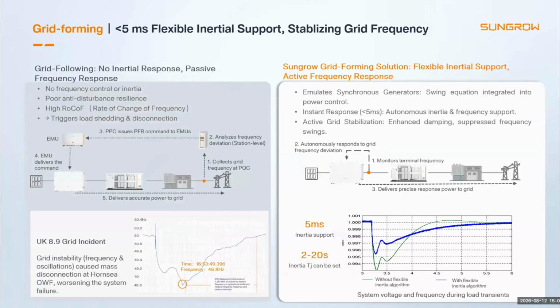One important grid forming function is the inertia support. Unlike synchronous generators, PV inverters have no physical rotating mass. Sungrow therefore emulates synchronous generator behavior through control algorithms. The inverter can respond to frequency changes within 5 milliseconds, providing very fast virtual inertia. Because this response happens locally at inverter level, it is much faster than waiting for a plant controller to measure, calculate, and send commands.